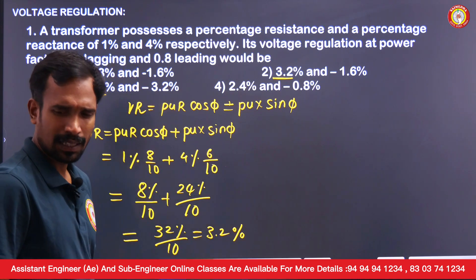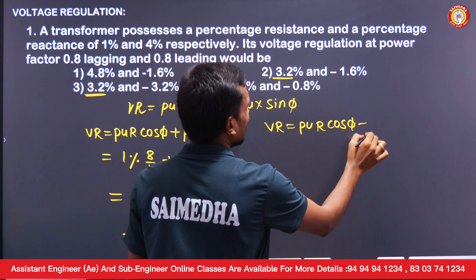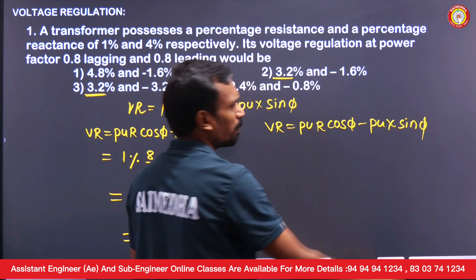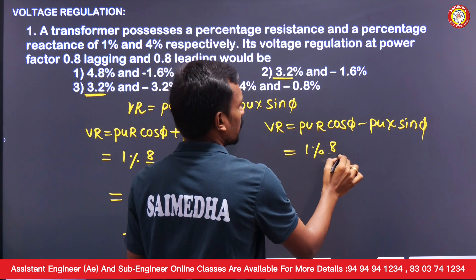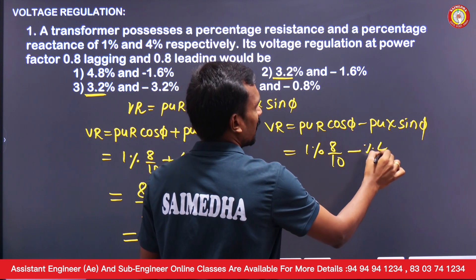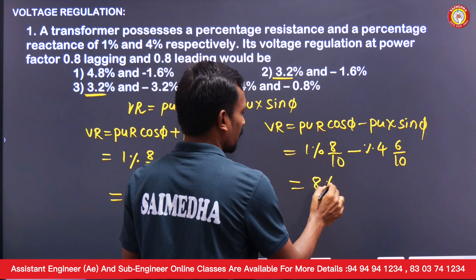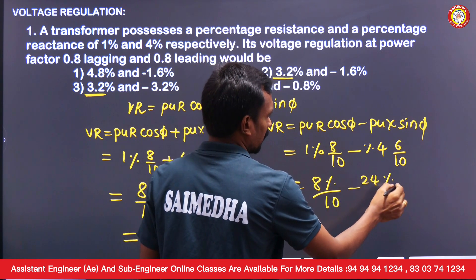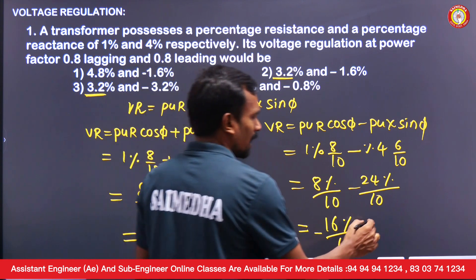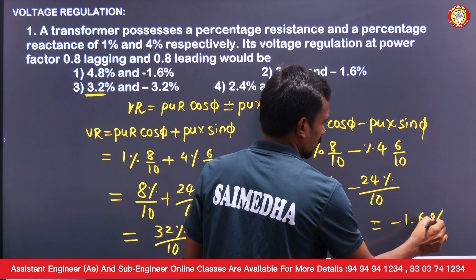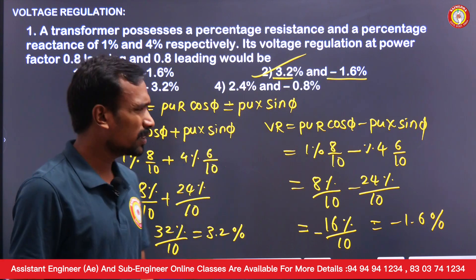For leading load, voltage regulation = per unit R × cos φ − per unit X × sin φ. Per unit R is 1%, cos φ is 0.8, per unit X is 4%, sin φ is 0.6. So: 8%/10 − 24%/10 = −16%/10 = −1.6%. The answer is −1.6%. This is a repeated exam-level question expected for diploma level.